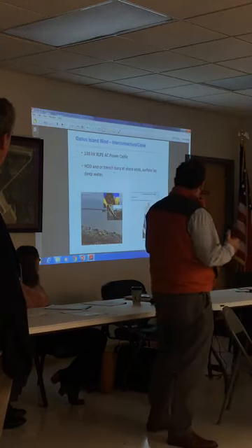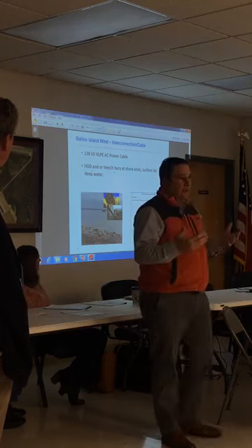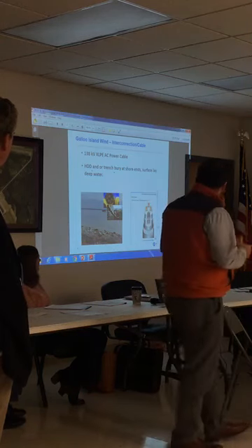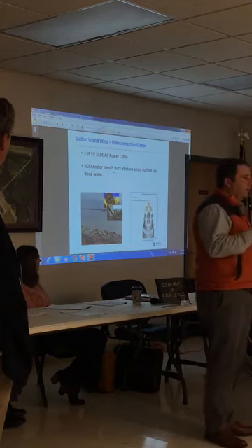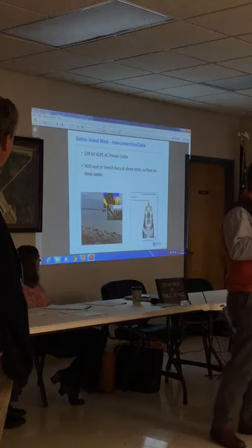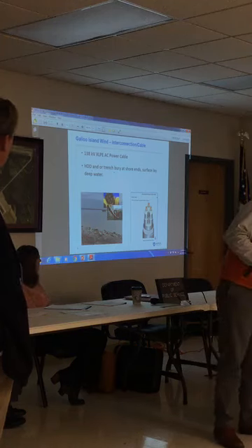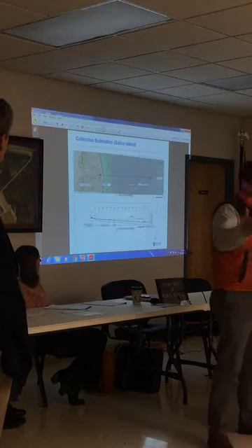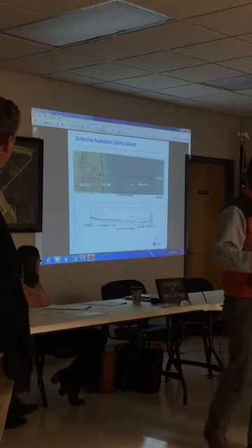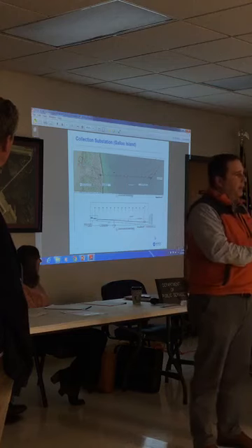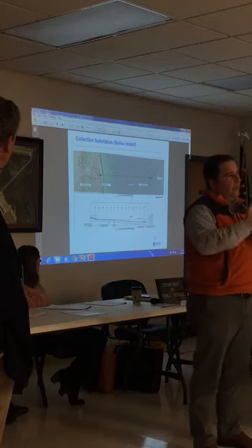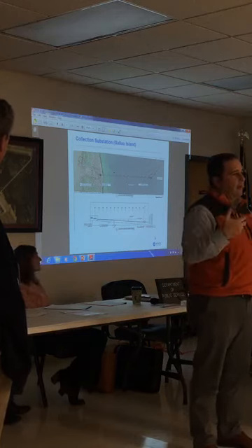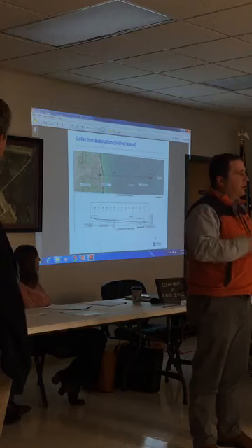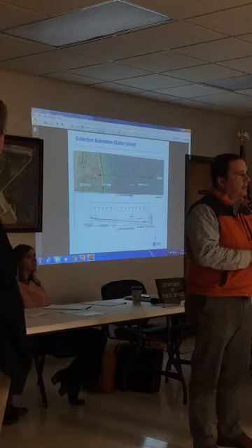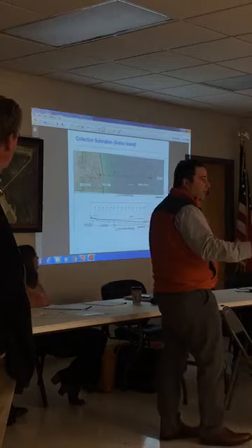This is a quick graphic demonstrating what the cable will be. It's a 138 kV line. It'll be HDD'd at the shoreline, with direct placement as we get into water depths. The reason we can do direct placement out in the water depths is because of the depth of the lake. An ice scour study showed that once you hit a certain depth, ice scour is not anticipated to be a concern, so direct placement is an adequate method for laying the cable.